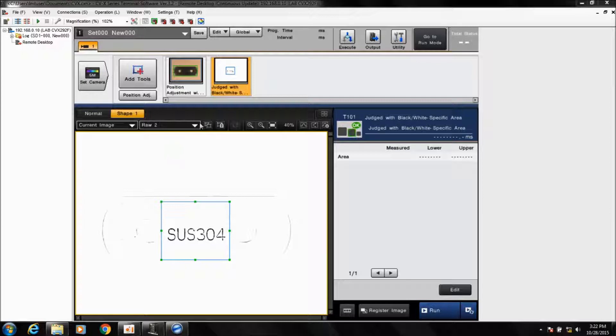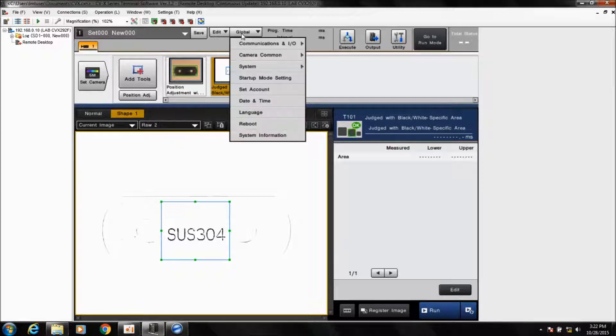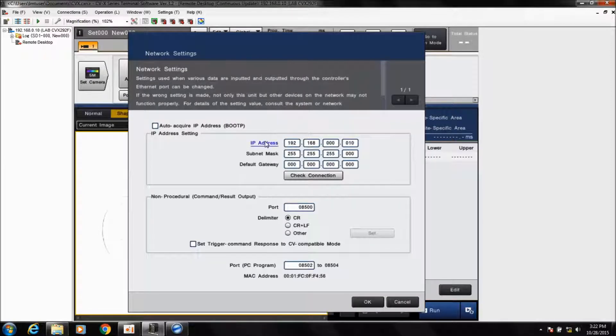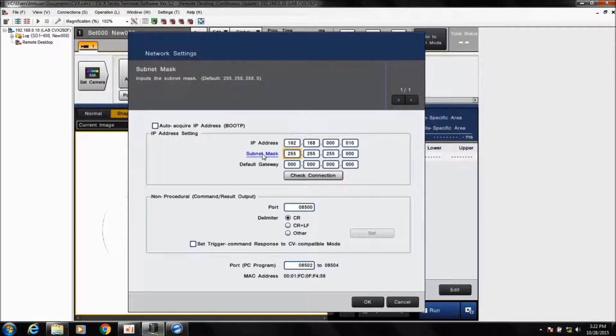The first step in the Ethernet IP setup is under the global settings. You need to set up the CVX controller to have the correct IP address. This is done under Global > Communications IO > Network, where you can set the fixed IP address, subnet mask, and default gateway. These settings will vary depending on your setup. In our example, we're going to use the default address 192.168.0.10.